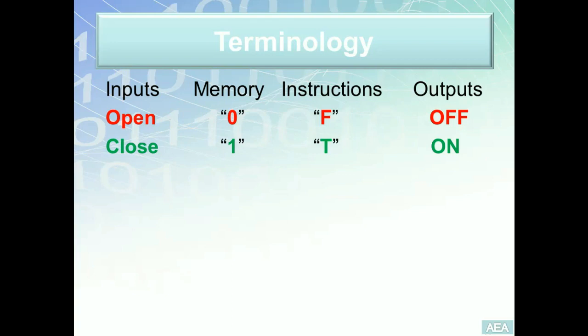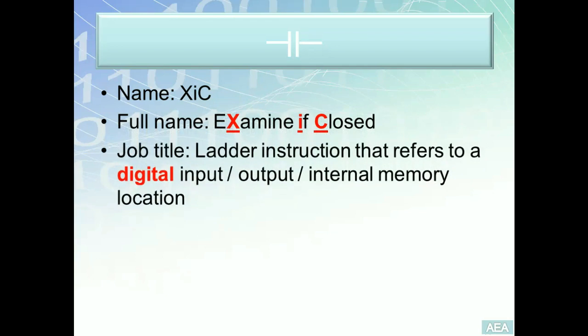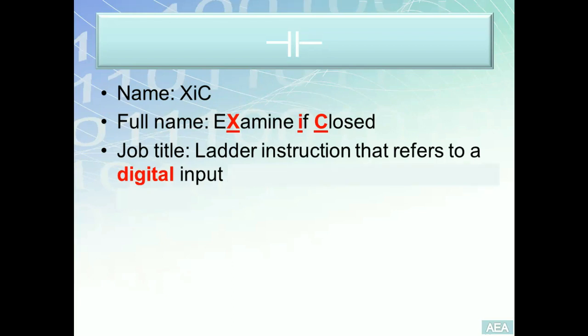It's really important to understand this simple concept because it will help us understand the functionality of discrete instructions when we build or troubleshoot programs. The first instruction looks like this — its nickname is XIC, and the full name is Examine If Closed. From the previous slide, a closed state switch or input will be read in the PLC memory as logic one, so this instruction will examine if an input is actually read as one. It is a ladder instruction that refers to a digital input, output, or internal memory location.